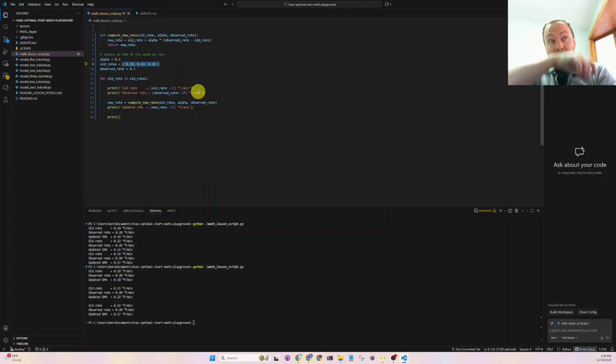Optimal start captures time and basically the delta temperature, which we talked about yesterday, and it records this. So probably one of the most important things it records. And then we're just using an exponential moving average to compute what would be the best rate to use now. So it's basically just smoothing out the data. That is the only thing it's doing.